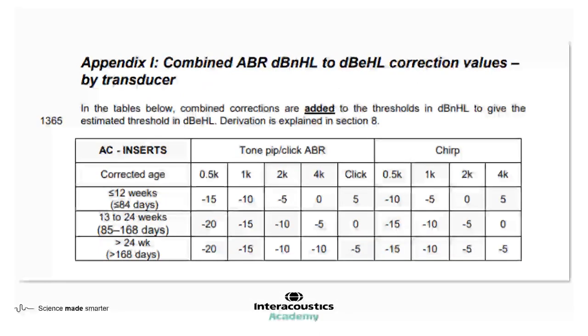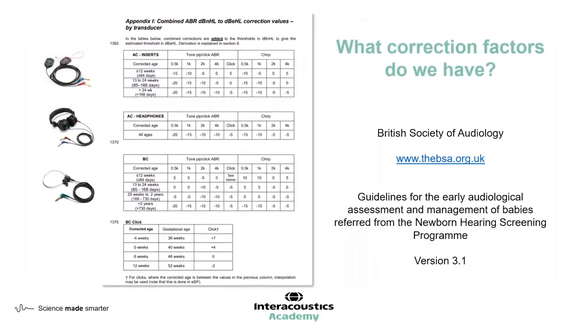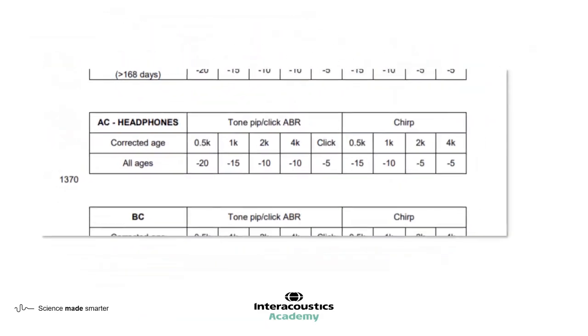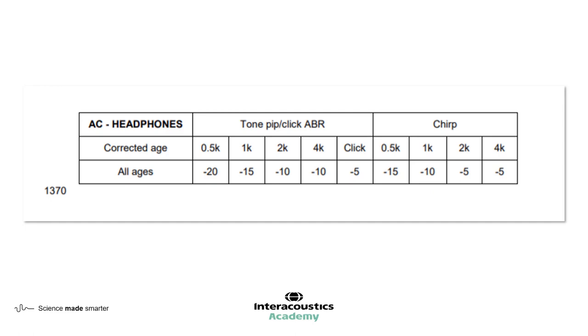It's really important to note that you must add these correction factors to the nHL values. You'll see that some are positive numbers and some are negative numbers. Remember, we are adding this correction factor value to our nHL number in order to get eHL values. So if you add a positive number, you simply add it, but if you add a negative number, you actually subtract it. Here we can see the correction factors for inserts, and you'll notice there are different stimuli. Next up, we can have a look at the correction factors for headphones, and we'll go into more detail about why there are limited age brackets here later.